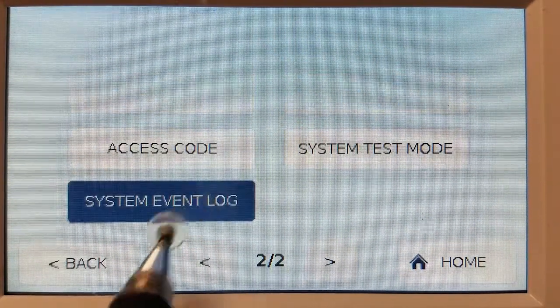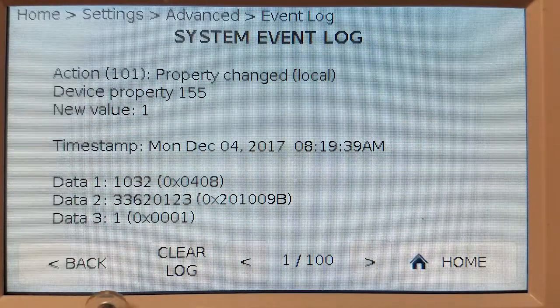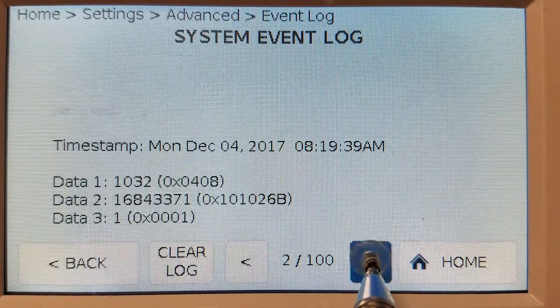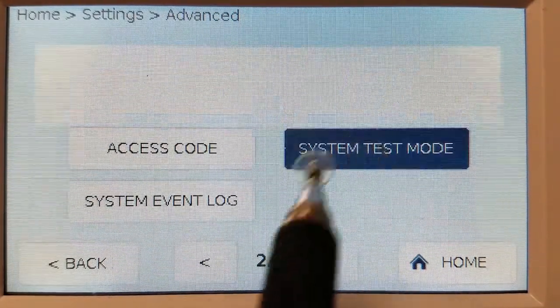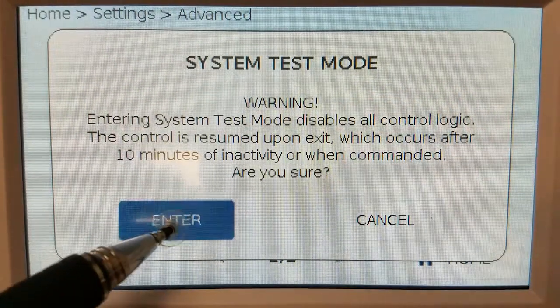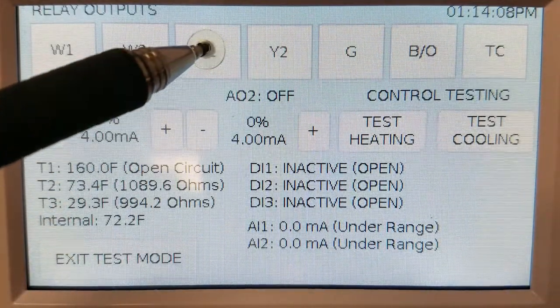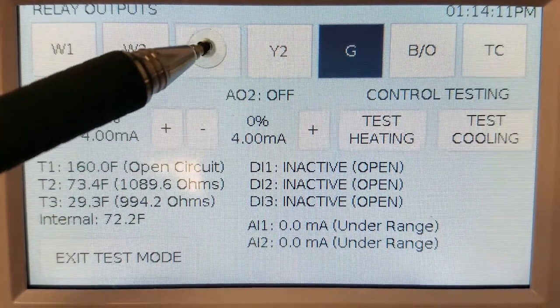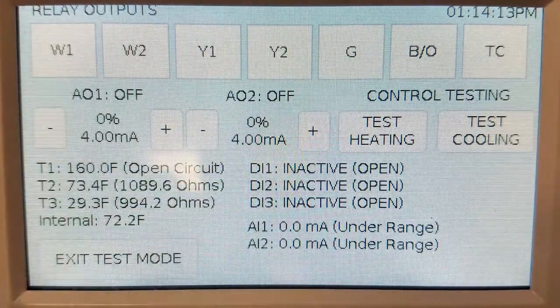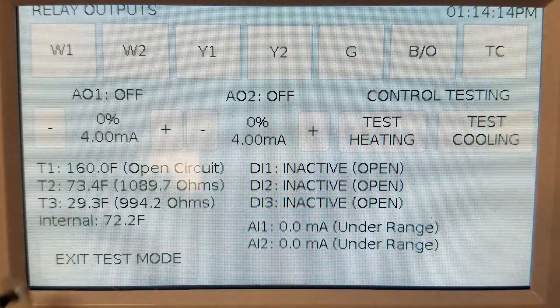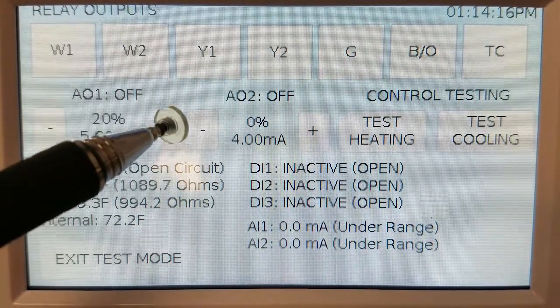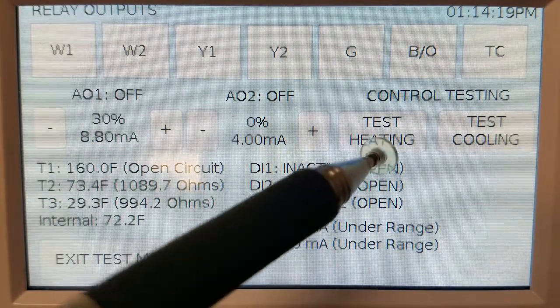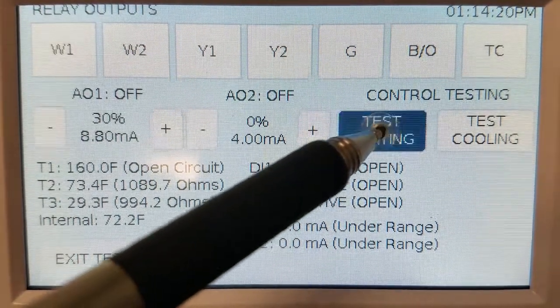A system event log shows every change made by BACnet device property, including a timestamp. The system test mode provides a great way to commission and test equipment by cycling on and off fans, heating and cooling stages, modulating the outputs, and all the while seeing the feedback from the remote sensors and digital input. There's even one-button testing for heating and cooling.